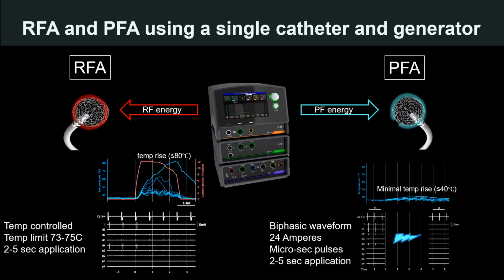PFA energy is delivered with a biphasic waveform in a microsecond range with current output around 24 amperes. With each application, multiple pulses are delivered during a time period of 2 to 5 seconds. The generator can also deliver RF energy in a temperature-controlled manner with 2 to 5 seconds per application with a limit of 75 degrees Celsius. As we can see in the graph, during RF ablation, temperature rise is sensed by the thermocouples, and this limits the current output, while in PFA we see minimal, if any, temperature rise. In both cases, EGMs are attenuated during the ablation and afterwards.